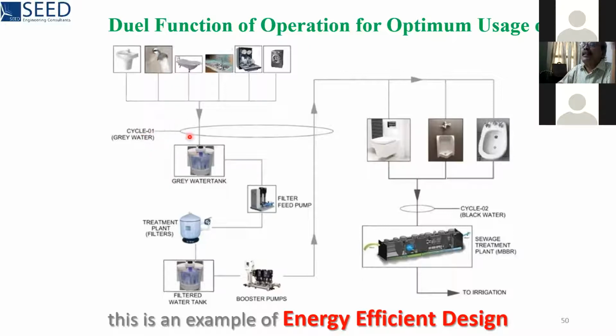From that 700 liters, 300 liters you are going through a simple filtration and disinfection process, and then you are going to use it for flushing the toilets, the urinals, and the bidet. So now you have completed your grey water cycle, and you are using that water for your black water cycle, and then it is going to the sewage treatment plant, where treated sewage effluent is used for irrigation purpose or for cooling tower makeup, and in some cases even for flushing the toilet. The slurry produced by the sewage treatment plant is a good manure which can be used for agriculture.